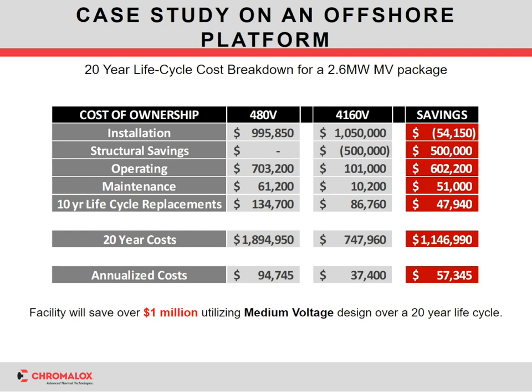So when we look at the long-term case, again, the 20-year life cycle, factoring in the $500,000 savings, now the medium voltage solution really began to shine. Not only from the installation savings, but again, the operational savings. As I mentioned earlier, you can see where a medium voltage system operates at close to 99% efficiency, so that saves them almost $600,000 in energy savings, delivering all that power directly to the process. And then lastly, with the maintenance and the replacement parts, there's simply less parts to worry about over the life cycle of the product, less products to fail. So ultimately, when we look at the life cycle over a 20-year lifespan of this product, the facility is going to be able to save over $1 million utilizing a medium voltage solution for this product.